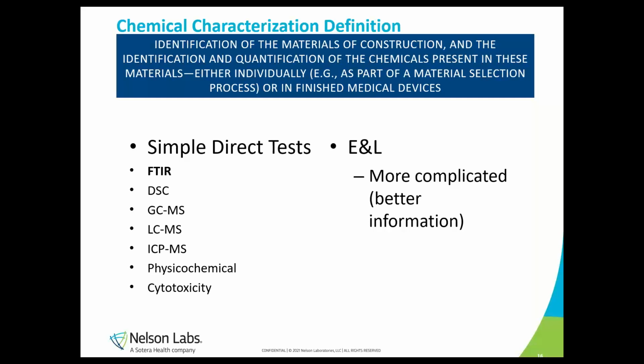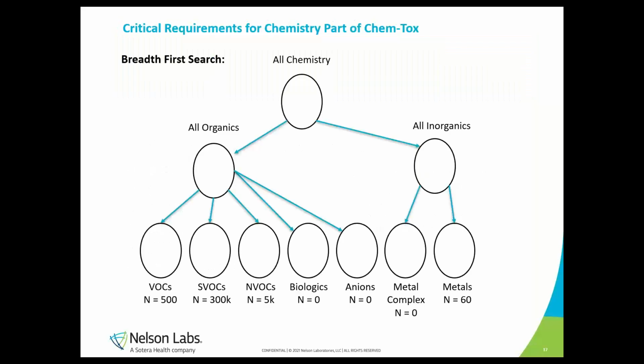The other thing that a lot of people look at as a tool for this is cytotoxicity, which we'll talk about. And cytotox is a great tool for changes. I just have to warn you, cytotox is pretty sensitive. So if you fail, that doesn't mean that your change is now going to hurt somebody. But if you passed on your previous device and you're failing on your new device, it does mean we have to evaluate what's different, and then understand if it is a patient risk or not. So, really high level, I want to make sure I give John time to talk on his side, but this is chemistry in a nutshell.